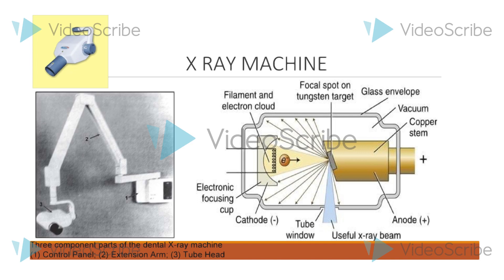The anode consists of tungsten target embedded in a copper stem. The target converts kinetic energy of electrons into X-rays. The copper stem is a good thermal conductor and removes heat from the tungsten and reduces the target melting.